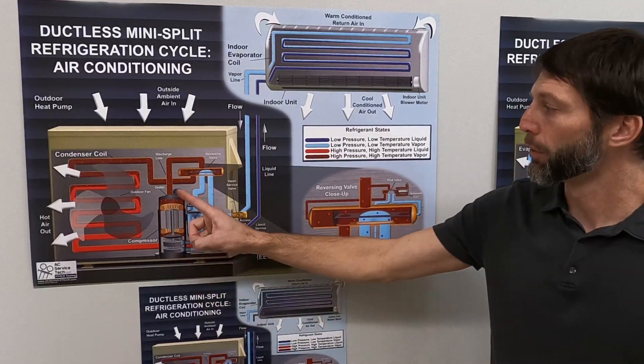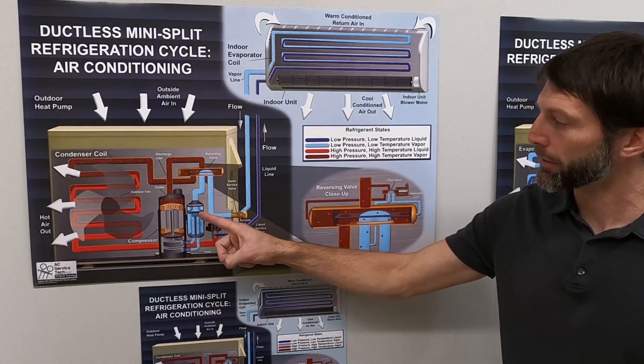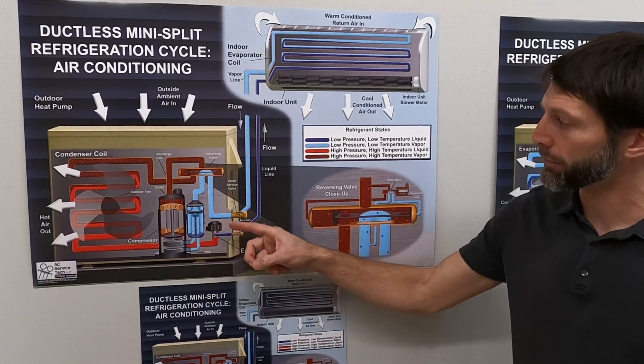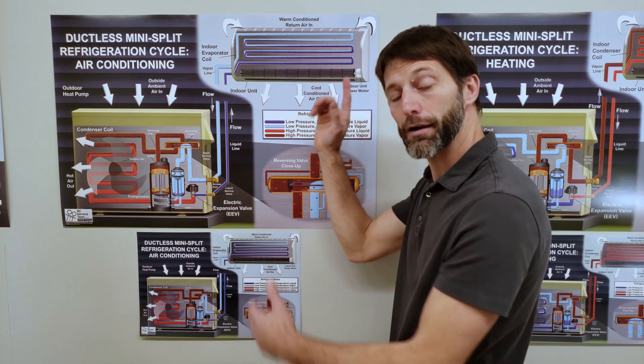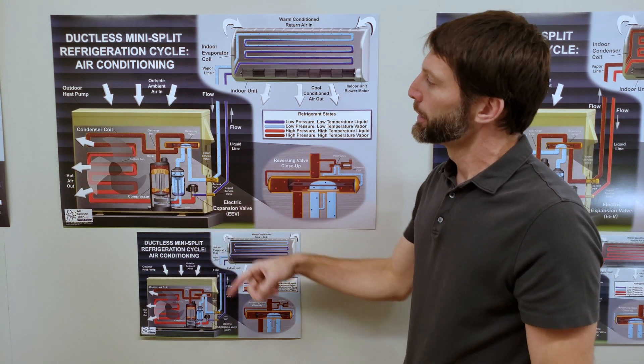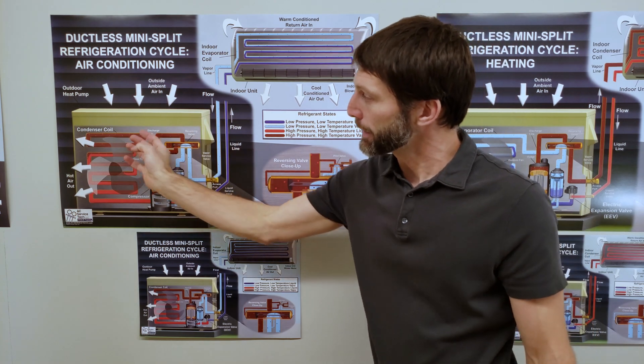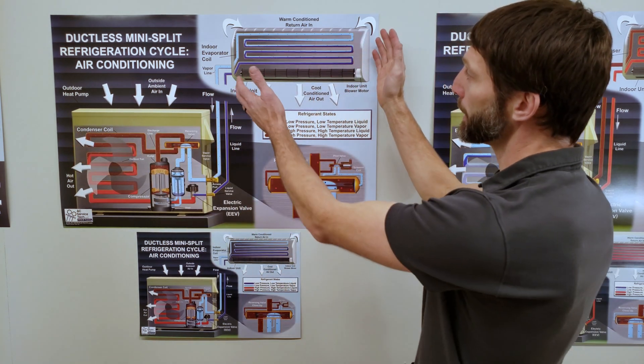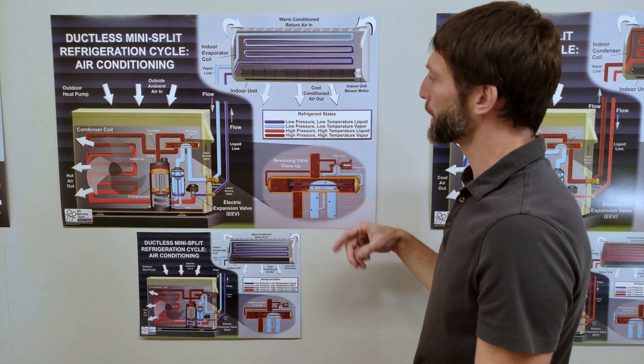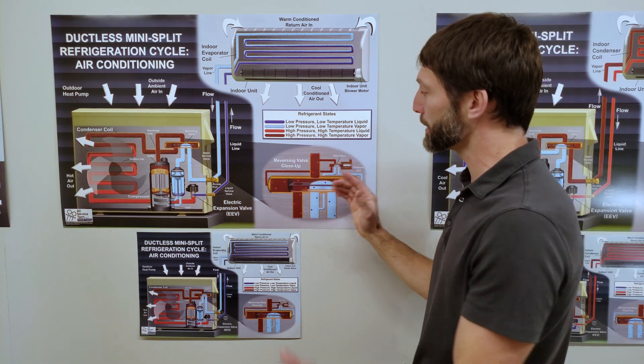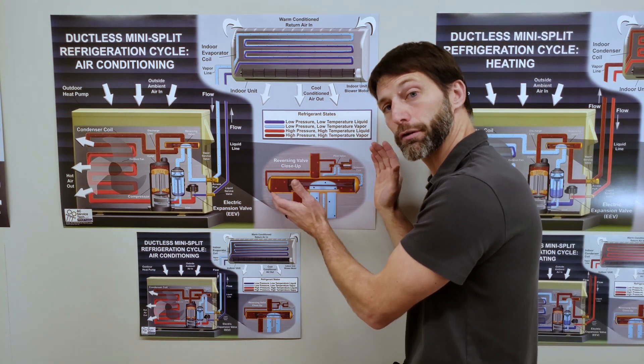Right here you have the ductless mini split refrigeration cycle in air conditioning mode. You have your rotary compressor and your accumulator. You have your EEV metering device. You don't have two metering devices here, you have one and it's located in the outdoor unit. You are rejecting the heat outside and absorbing the heat inside into the refrigerant. You can once again see your refrigerant state and you have a close up view of the reversing valve.